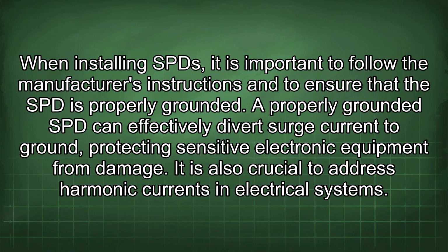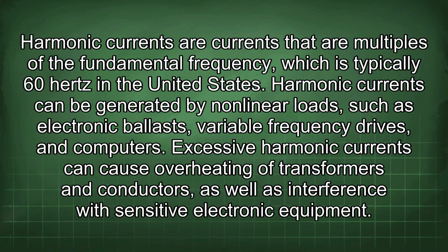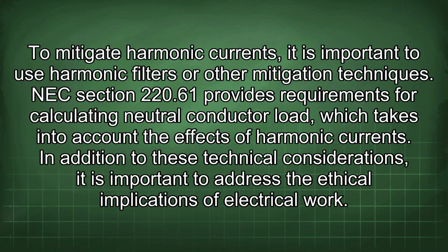It is also crucial to address harmonic currents in electrical systems. Harmonic currents are currents that are multiples of the fundamental frequency, which is typically 60 Hz in the United States. Harmonic currents can be generated by nonlinear loads such as electronic ballasts, variable frequency drives, and computers. Excessive harmonic currents can cause overheating of transformers and conductors, as well as interference with sensitive electronic equipment. To mitigate harmonic currents, it is important to use harmonic filters or other mitigation techniques.